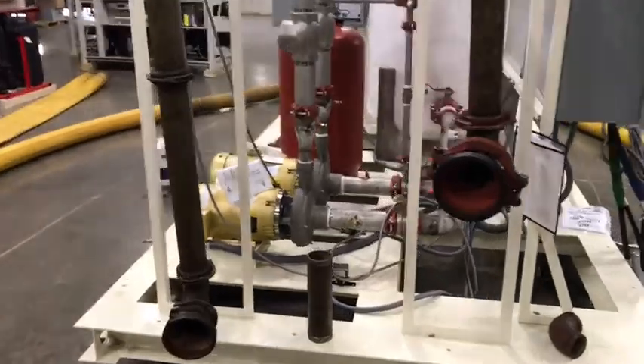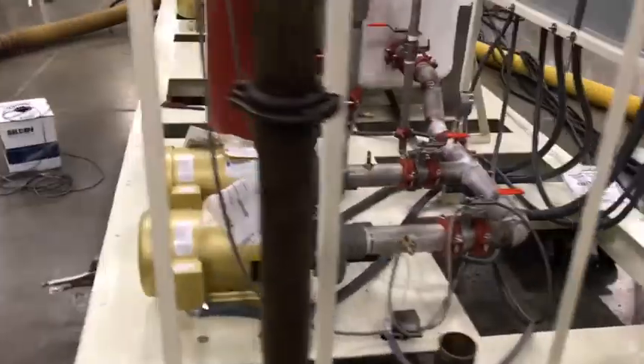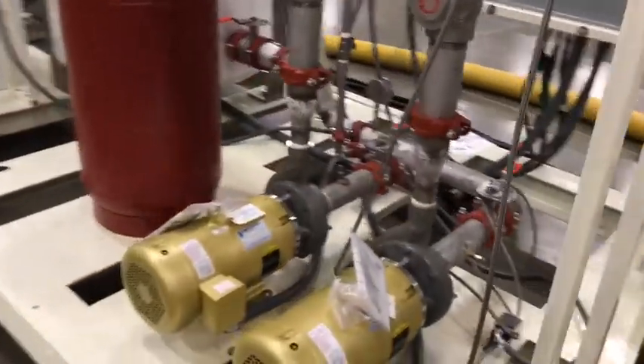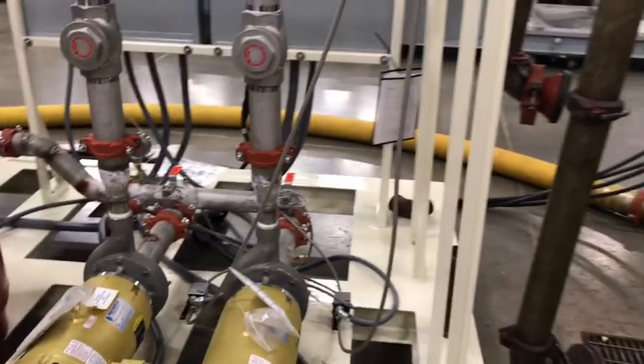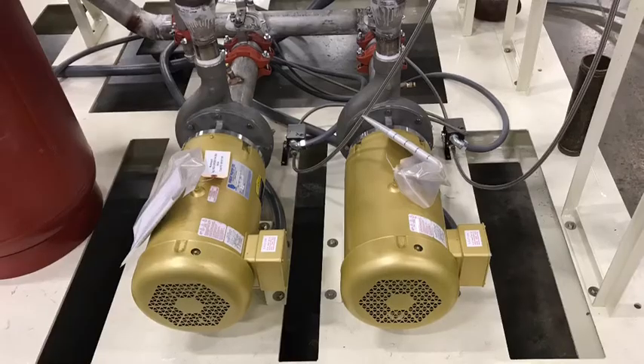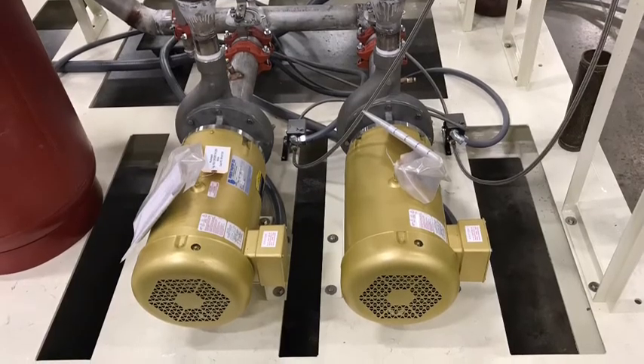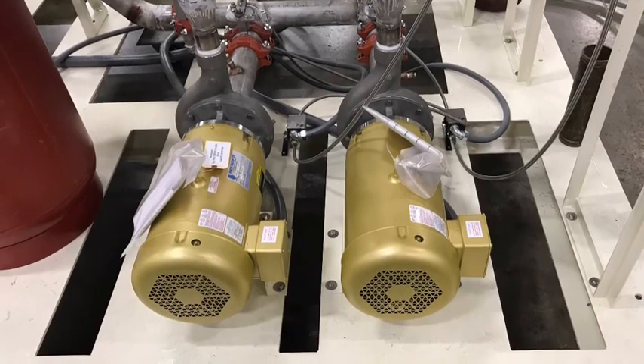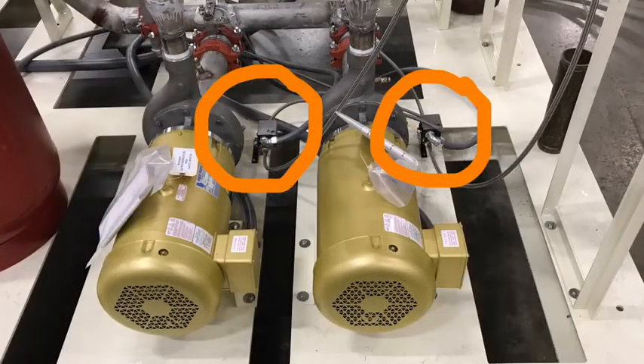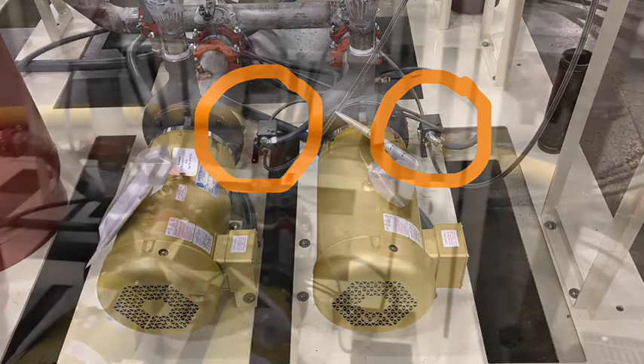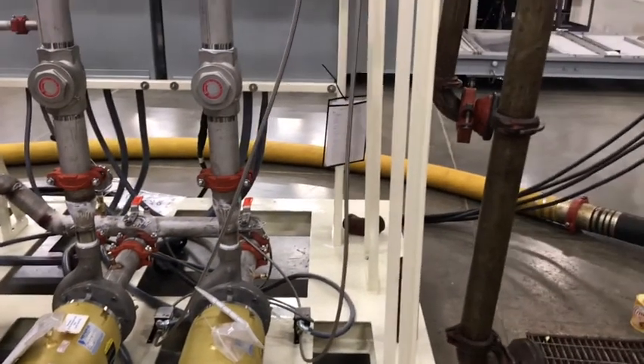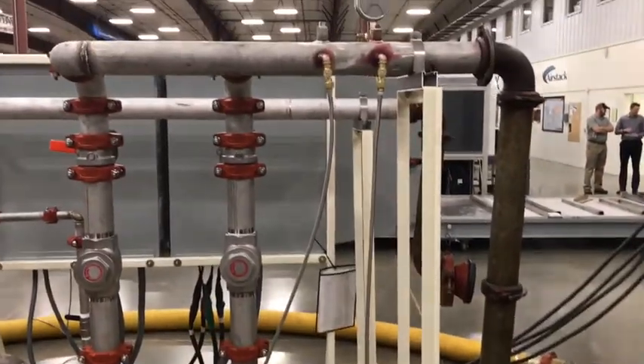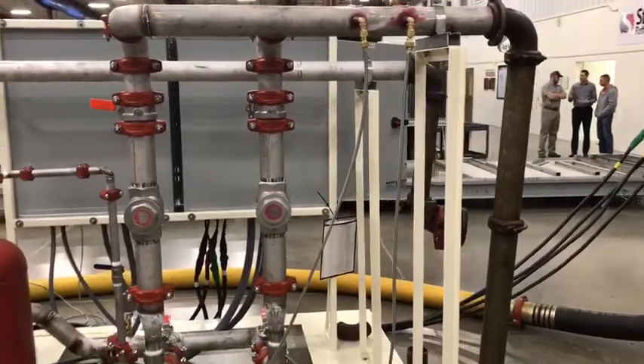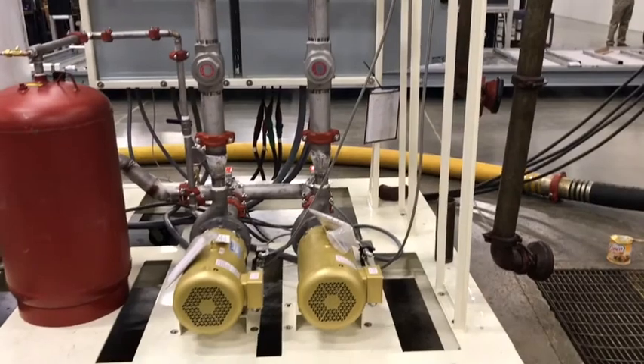So this is the smaller two circulating pumps and the supply and return to the room being served. I'll have a close-up view here, and we'll look at the differential pressure switches that serve as a proof of flow for rotating pumps in case of failure. Those are shown here circled in orange. We'll continue panning to the left, and we'll see the three types of tanks that we have in this project.